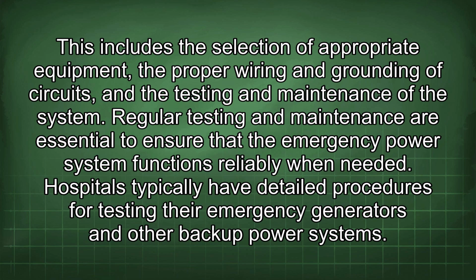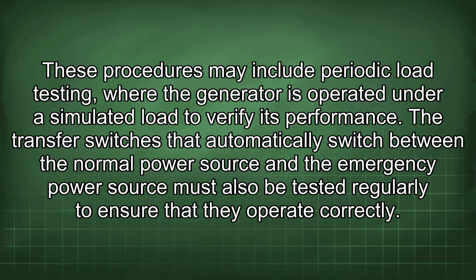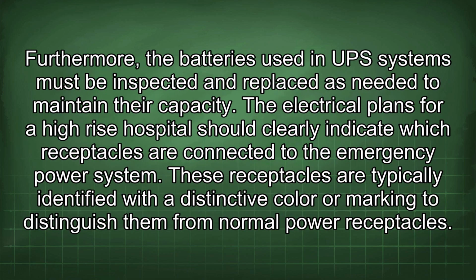Regular testing and maintenance are essential to ensure that the emergency power system functions reliably when needed. Hospitals typically have detailed procedures for testing their emergency generators and other backup power systems. These procedures may include periodic load testing, where the generator is operated under a simulated load to verify its performance. Transfer switches that automatically switch between the normal power source and the emergency power source must also be tested regularly to ensure that they operate correctly. Furthermore, the batteries used in UPS systems must be inspected and replaced as needed to maintain their capacity.